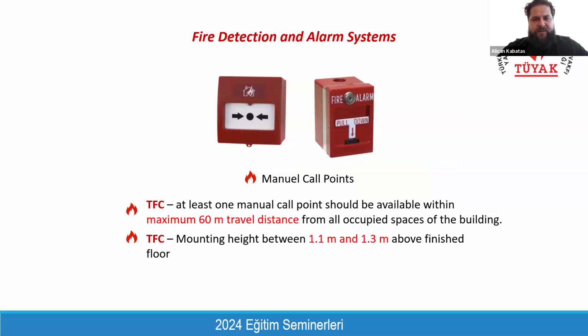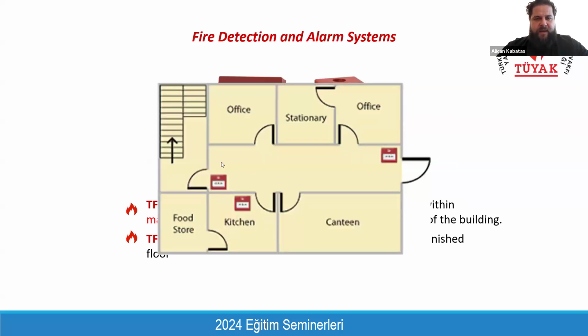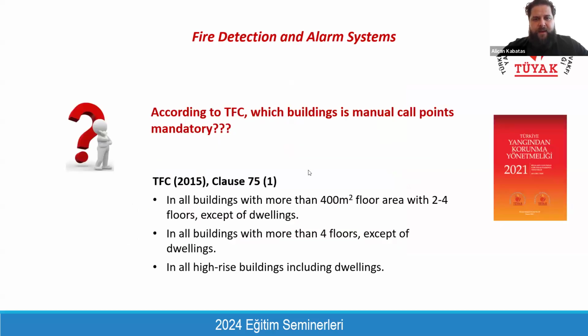And we will have manual call points, which is not architecturally good-looking equipment, but it's mandatory. It should be mounted between 1.1 and 1.3 meters so that everyone can use it. And you will see it on your main corridors. There is no alternative to these manual call points. And as you can see, at the entrance to the exit access routes, just next to the exit access doors, we will have some manual fire call points. According to the Turkish fire code, manual call points are required for this kind of building.